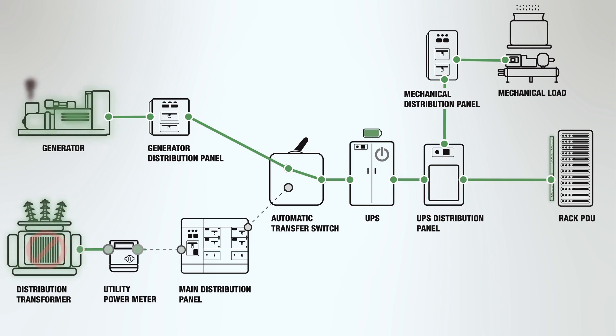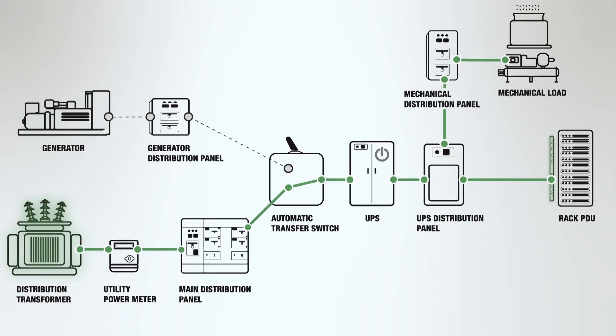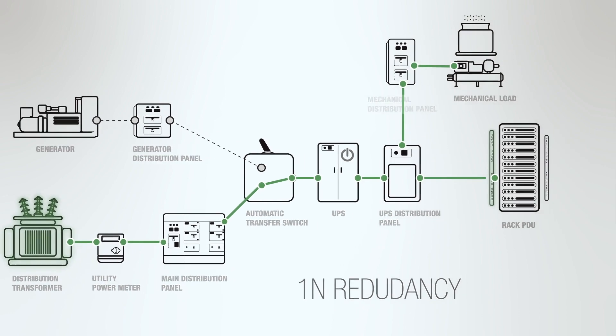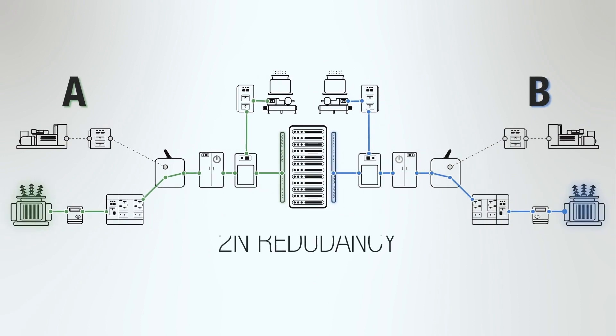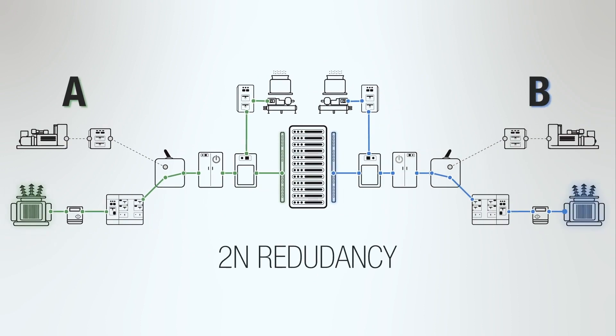When the utility feed comes back on, the ATS communicates back to the generators and allows them to go offline. This is an example of 1N redundancy, with a small percentage of redundancy to individual parts. Tier 3 and Tier 4 data centers require 2N redundancy, which is a mirrored system with two separate points of independent distribution, ultimately feeding two separate rack PDUs, and an AB feed that typically supplies power to A and B power supplies within the IT device for complete redundancy of power.